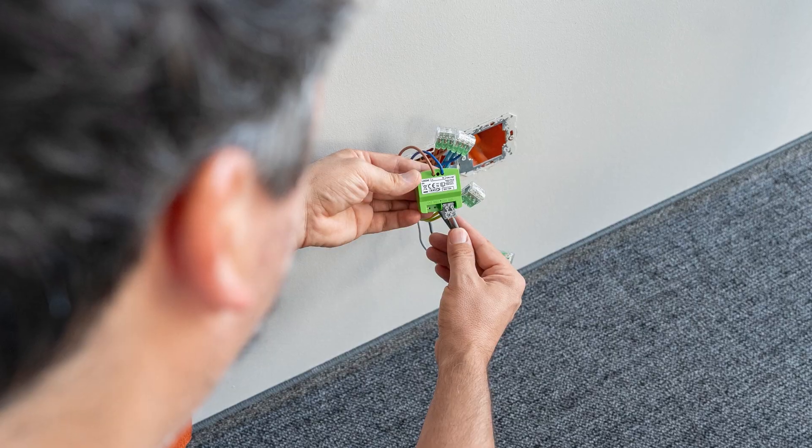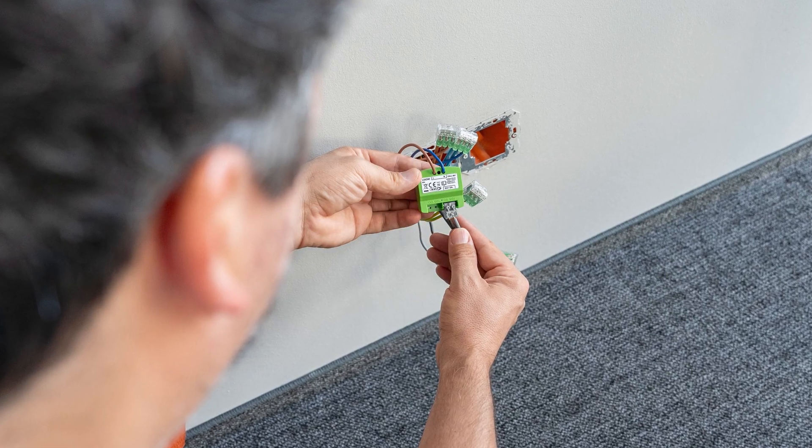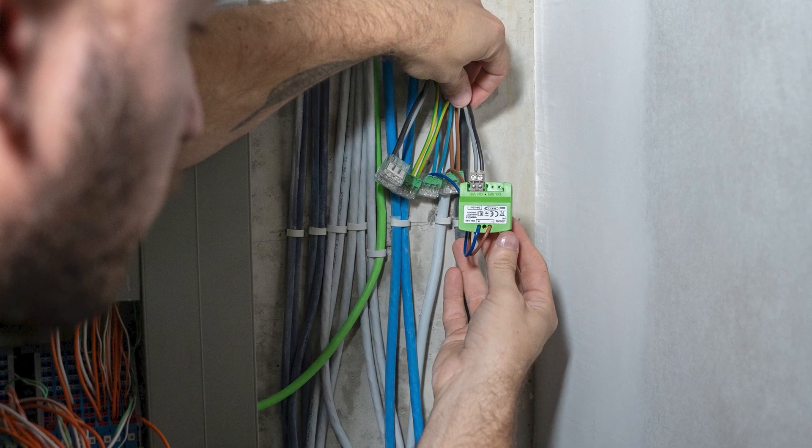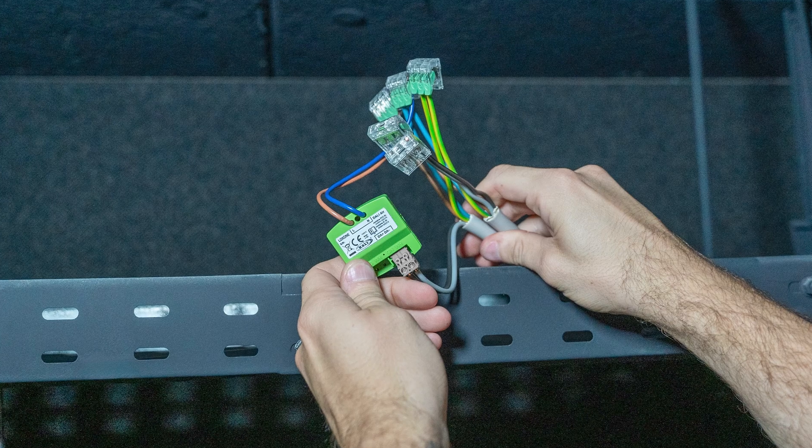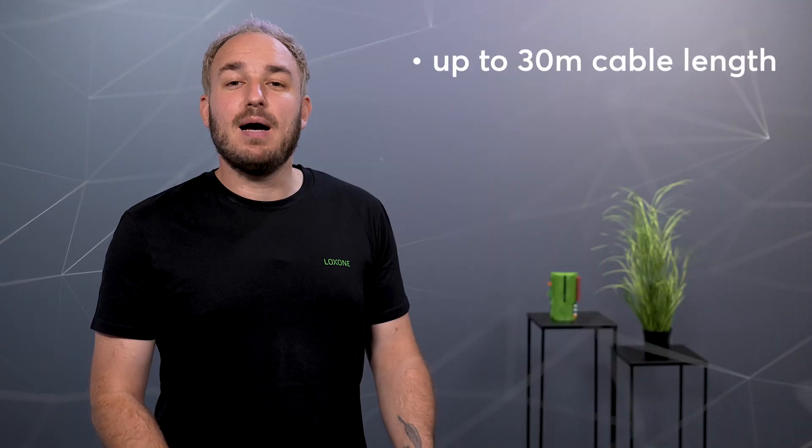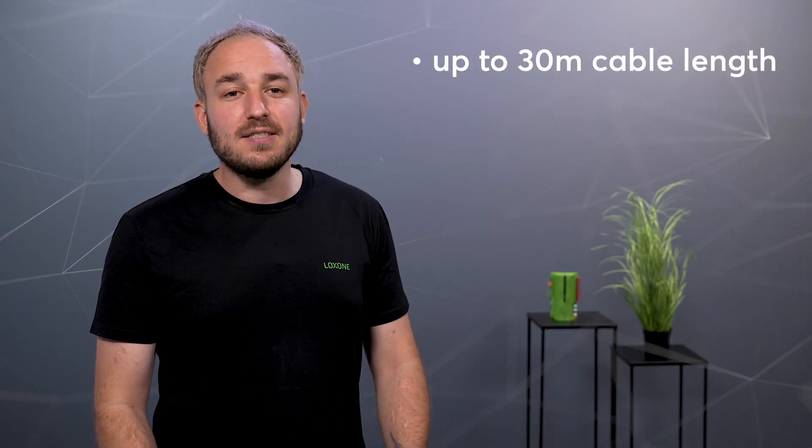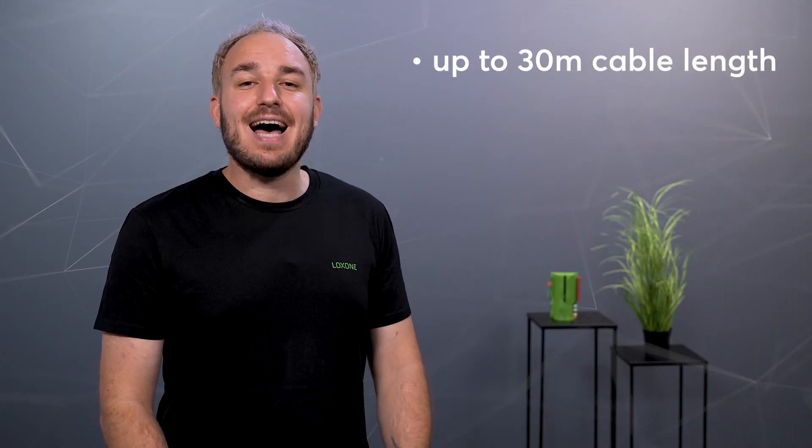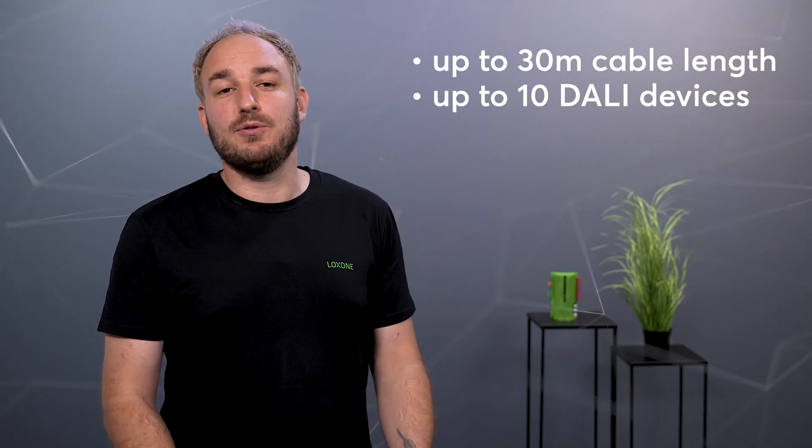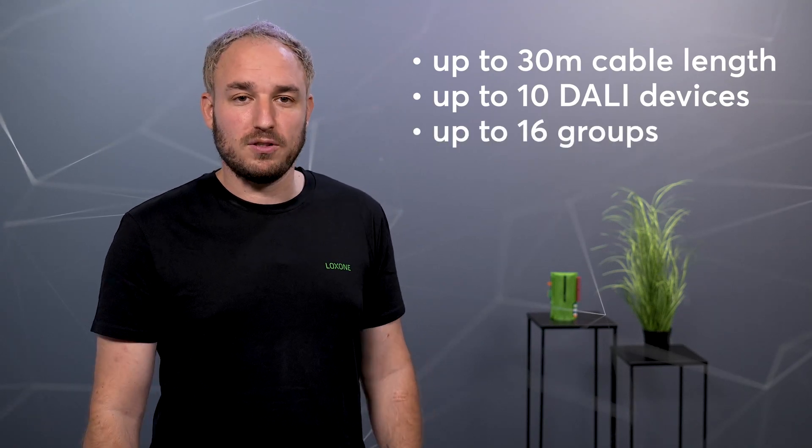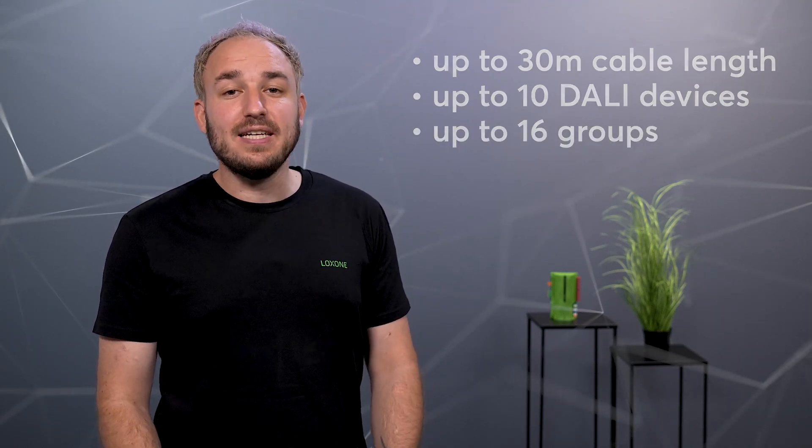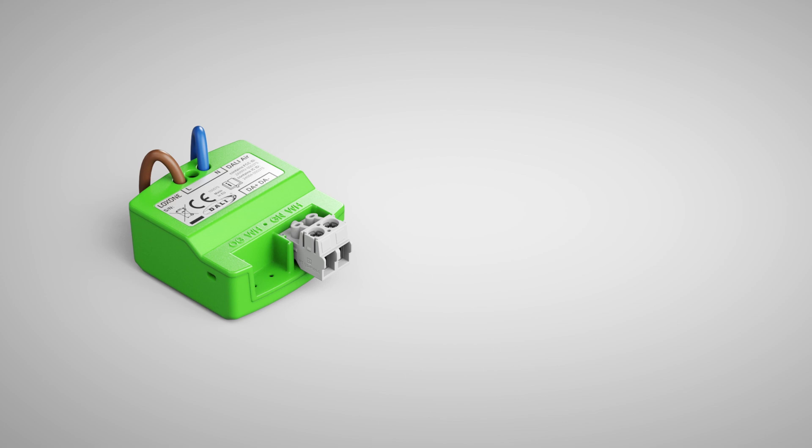Due to the compact design, the DALI Air can be easily installed in a flush-mounted box or on a cable tray. The cable length can be up to 30 meters, and 10 DALI devices can be taught in up to 16 groups. The DALI Air is officially DALI 2 certified.